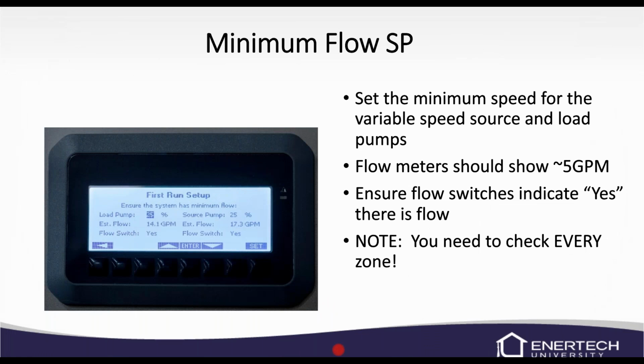The first thing we're going to do is set the minimum speed for the variable speed source and load pumps. What we need to see is a minimum flow of 5 GPM, and that'll set the parameter for the lowest that pump will ever run. Here we're showing 25 on the load and 25 on the source. Normally, that source pump is going to be somewhere between 45 and 60%, just what I've seen from experience.